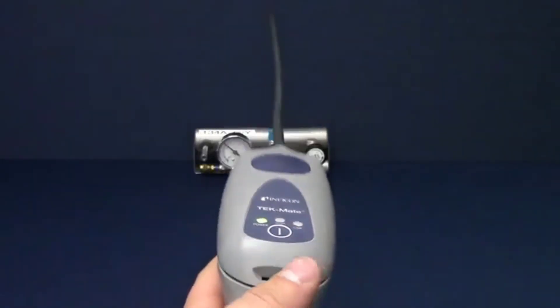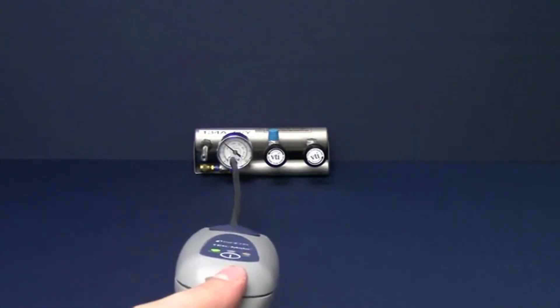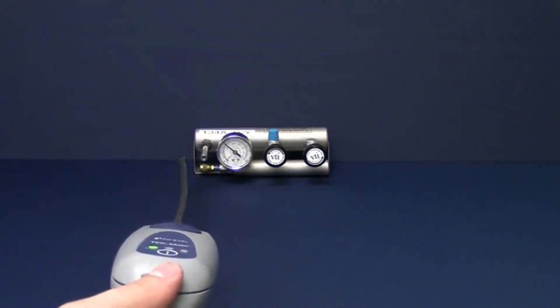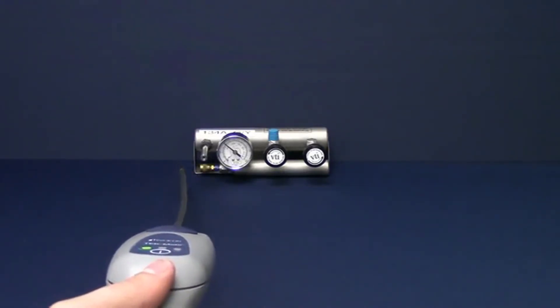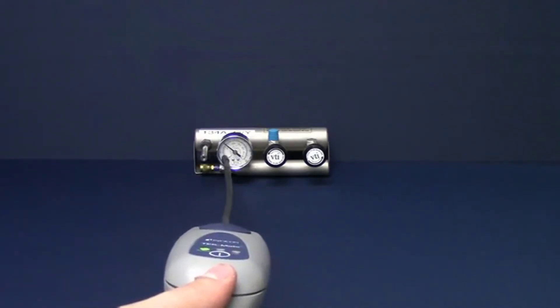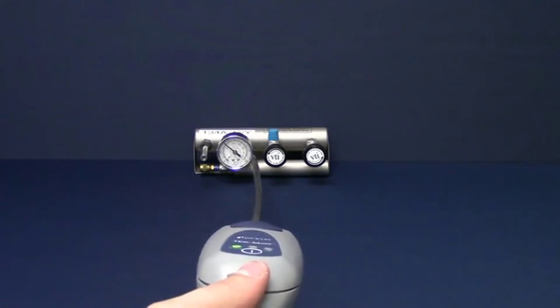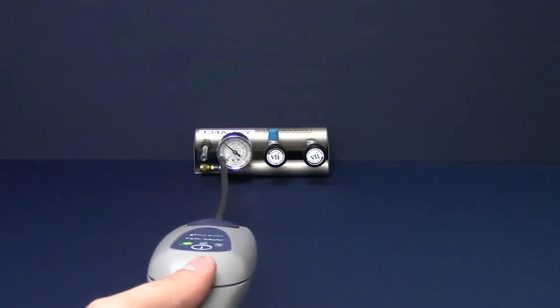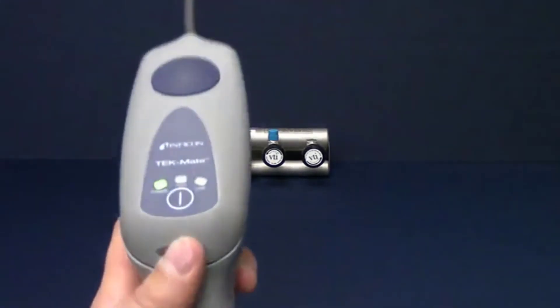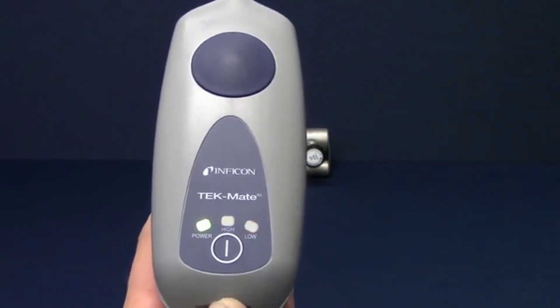Next, switch to low sensitivity by pressing the power button. Continue to move TEK-Mate through the leak source until you have narrowed the leak source down to a specific point. Keeping the probe in the same concentration of refrigerant for an extended amount of time will zero TEK-Mate to that concentration. Moving the probe away from that area will reset the zero point.